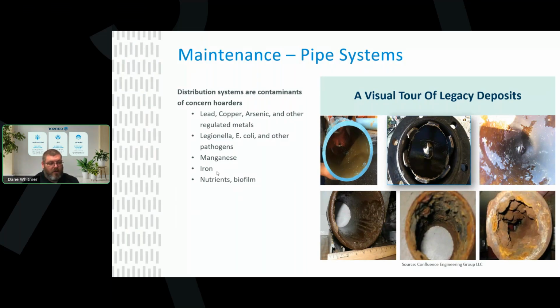So if you recall, a few years pre-COVID, there was Flint, Michigan, right? Flint, Michigan was the act of changing the water source, and that in turn had a different water quality and chemistry that ended up leaching all the buildup in the piping system that has occurred over decades of time, which then, once it reached any of those lead line pipes, started leaching into the water distribution system and became a major health problem. So we have to look at pipes as a maintenance item, because of these kinds of concepts.